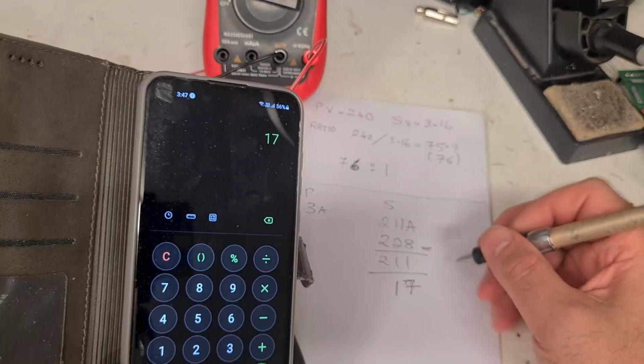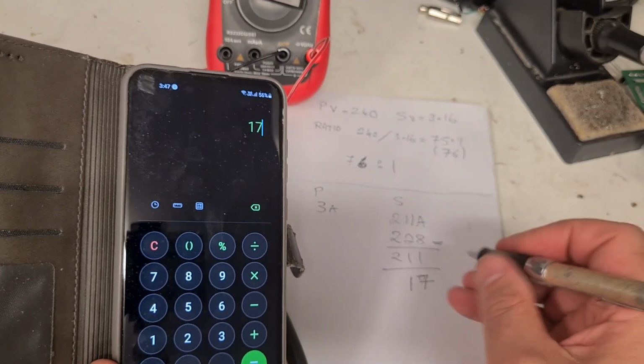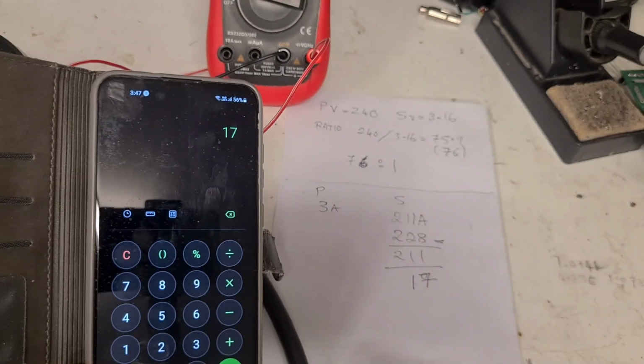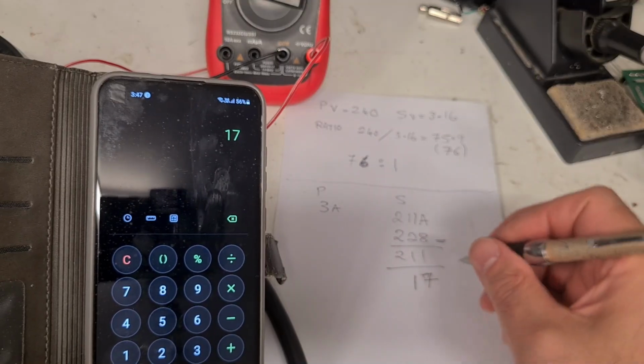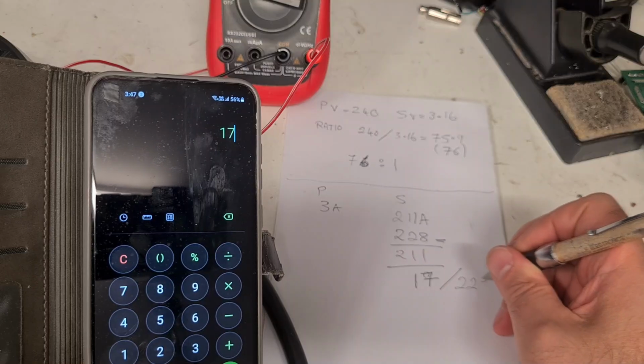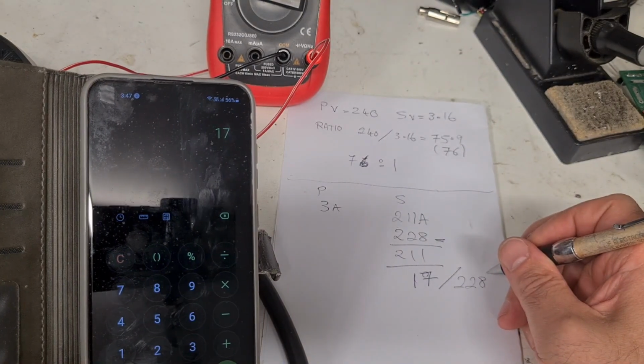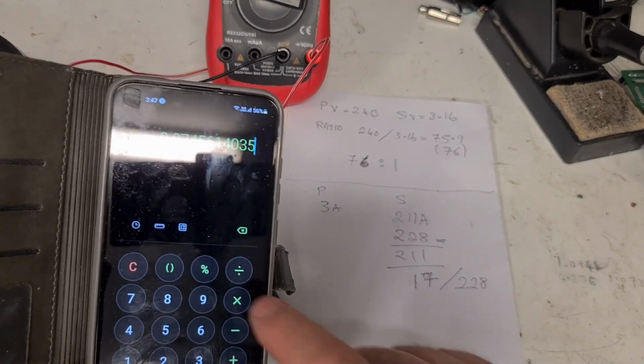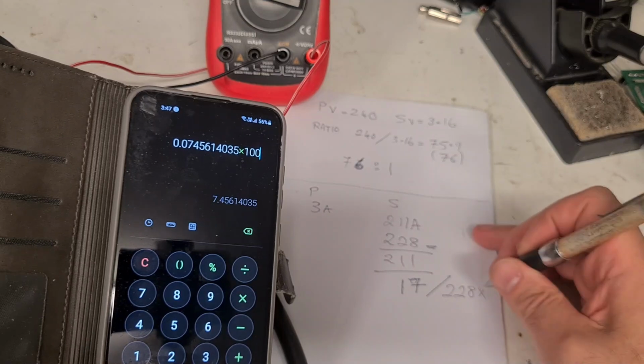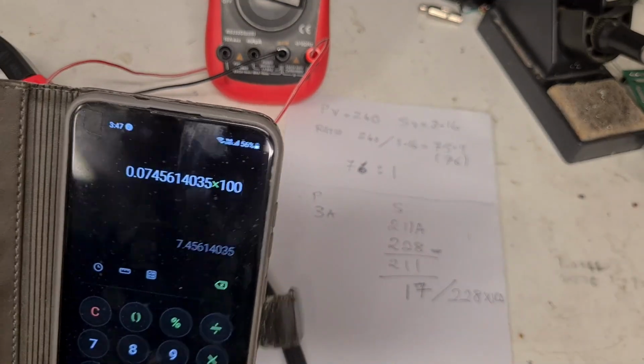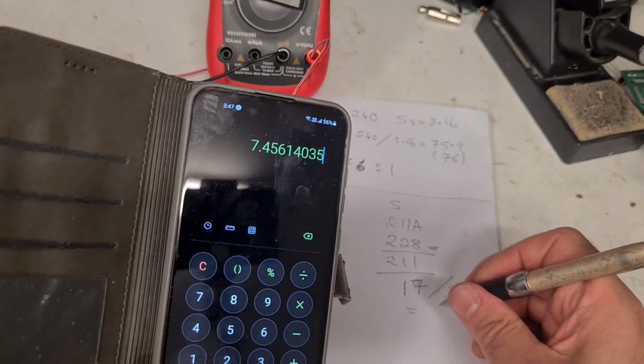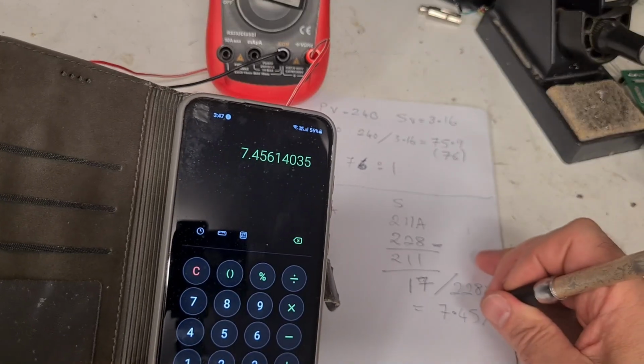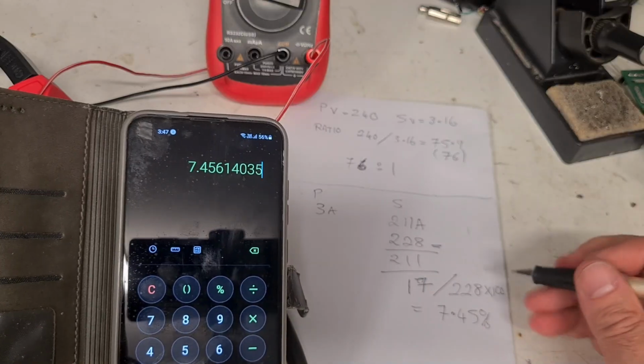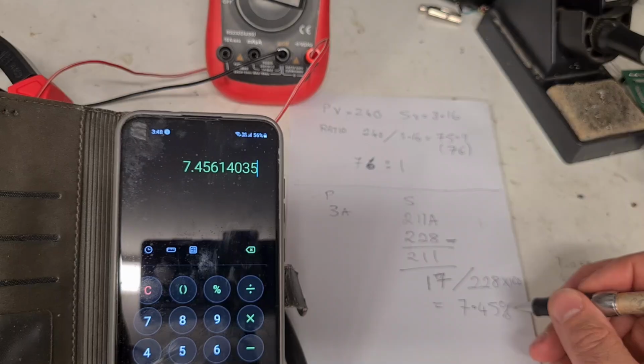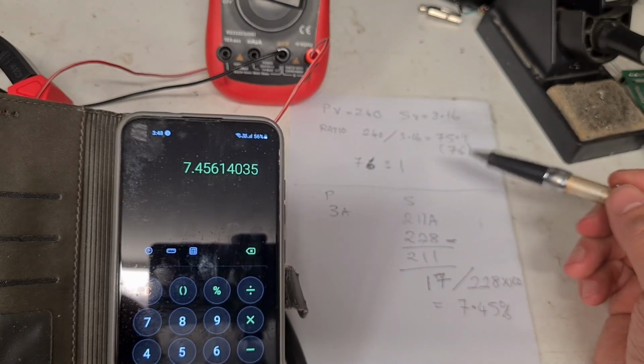Now I want to work out the percentage at this stage. So we do 17 divided by 228, times 100, which equals 7.45% less. And that's probably because of the shunts. So at this stage, I've lost 7.45% at 3 amps on the primary.